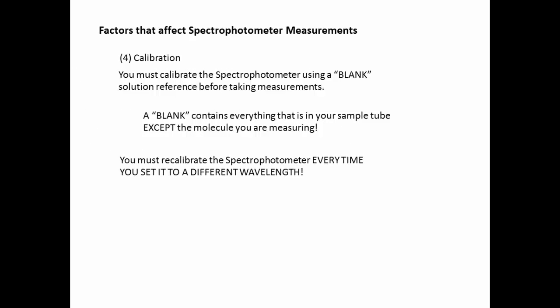And you must remember that the spectrophotometer must be recalibrated every time you set it to a different wavelength. If you calibrate the spectrophotometer at one wavelength and take multiple measurements at that same wavelength, you do not have to recalibrate it every time. But the moment you switch to a different wavelength, you must recalibrate it or you will not get accurate measurements.